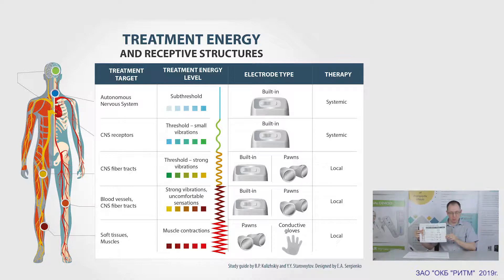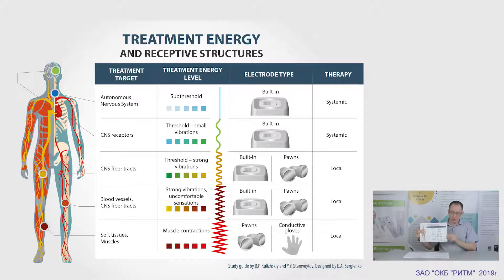The supra-threshold level of energy brings the nerves to a refractory state, and treatment becomes local. The device now focuses on the soft tissues. This level is used for myostimulation and treatment of the locomotor system. The main electrodes to use here are pads and conductive gloves.